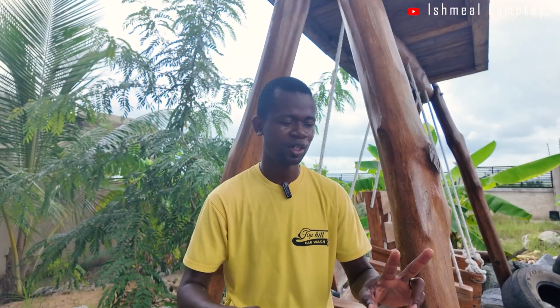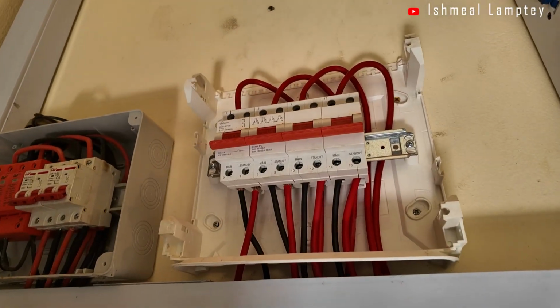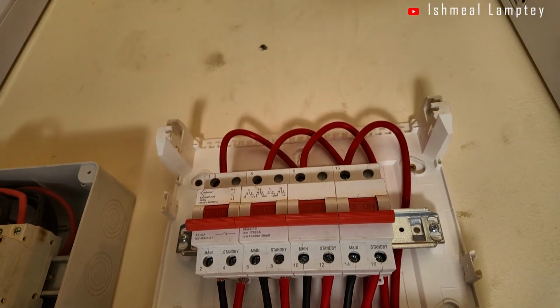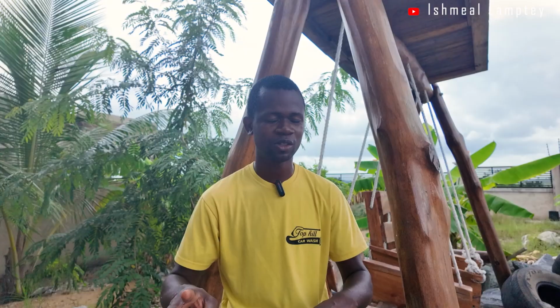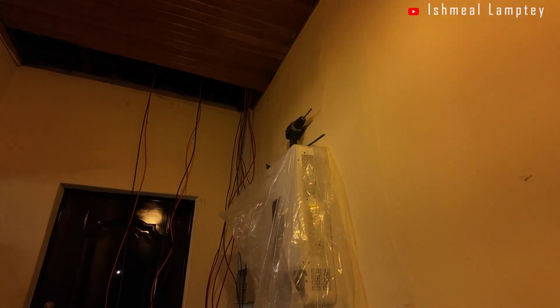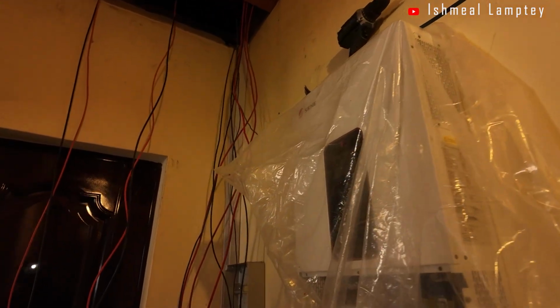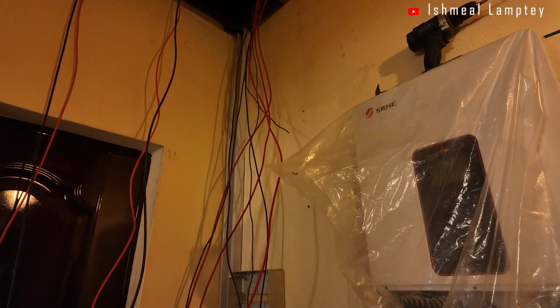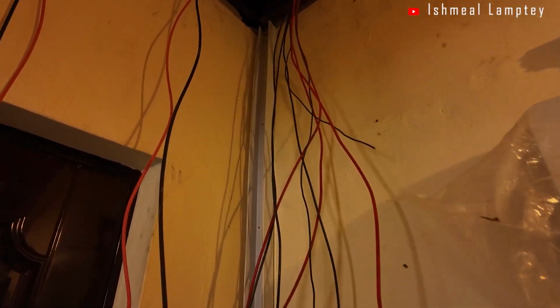Then aside from that, you have the PV cables as well. So you have 2 coming in from each panel, that is positive and negative, and then you also have another 2 coming in. So in all, the total quantity of cables we had to pull through the ceiling was about 12 or so. And it was easier to pull them because they already had an old system. We didn't want to mount trunking on the wall to pass the cable, so we wanted to have a clean job. That's how we went about that too.